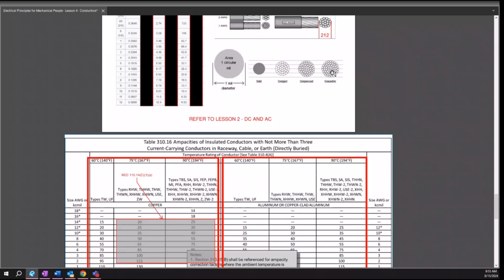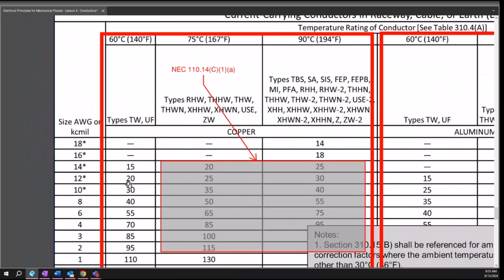However, if you turn the page in your Uglies to page 74, there's a whole new table: ampacities of insulated conductors, single insulated conductors in free air. And in that table, if you notice, for instance, number 12 in the 60C column is rated for 30 amps, whereas in here it's only rated for 20. Well, the reason you can get 10 more amps down that conductor in free air is because you don't have the insulation. That heat can rise and get out of there, and that's not going to melt the conductor. Oh, that makes sense.